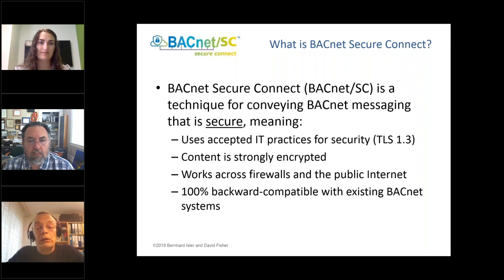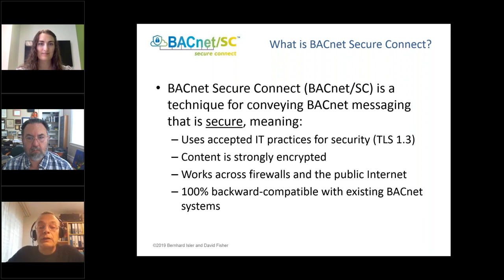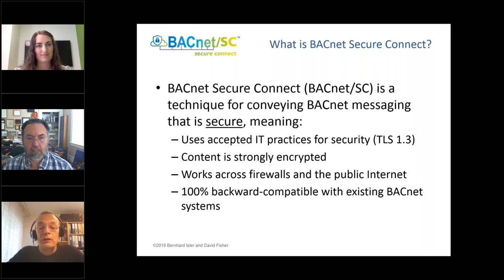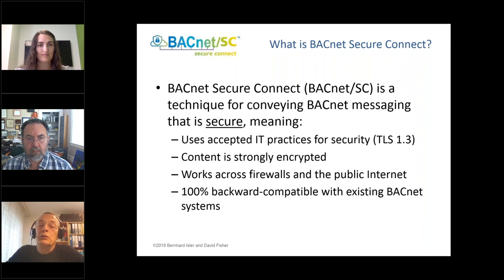The goal was always to provide IT friendliness and include security well known by IT departments. Currently we define the use of TLS version 1.3, and Secure Connect essentially sits on secure WebSockets, which allows it to pass through whatever IT environment — including support for DHCP, DNS, NATs, and firewalls — making BACnet a good citizen in IT department-managed networks.